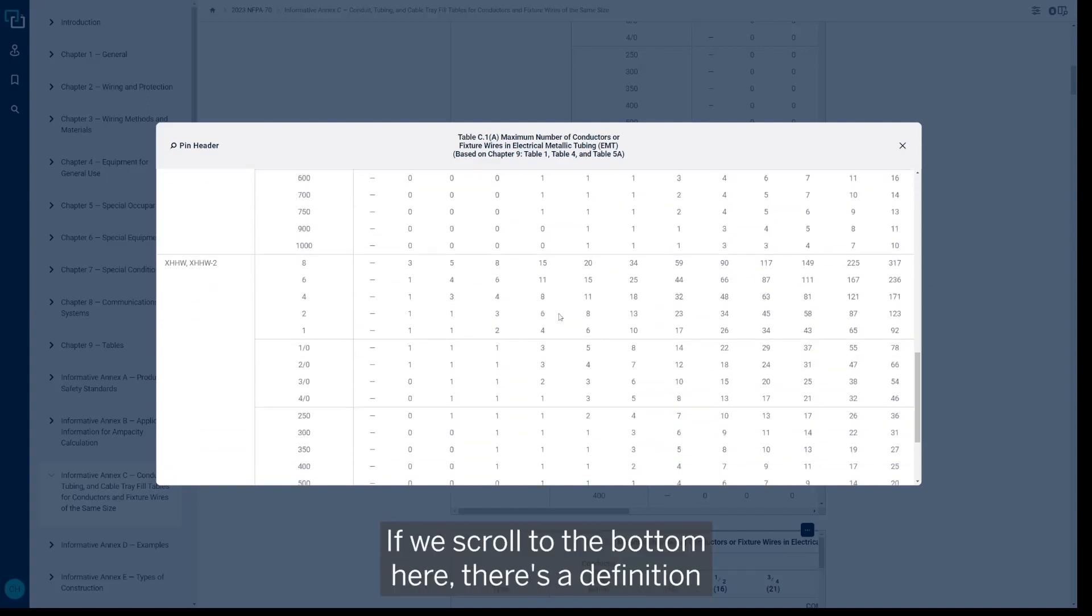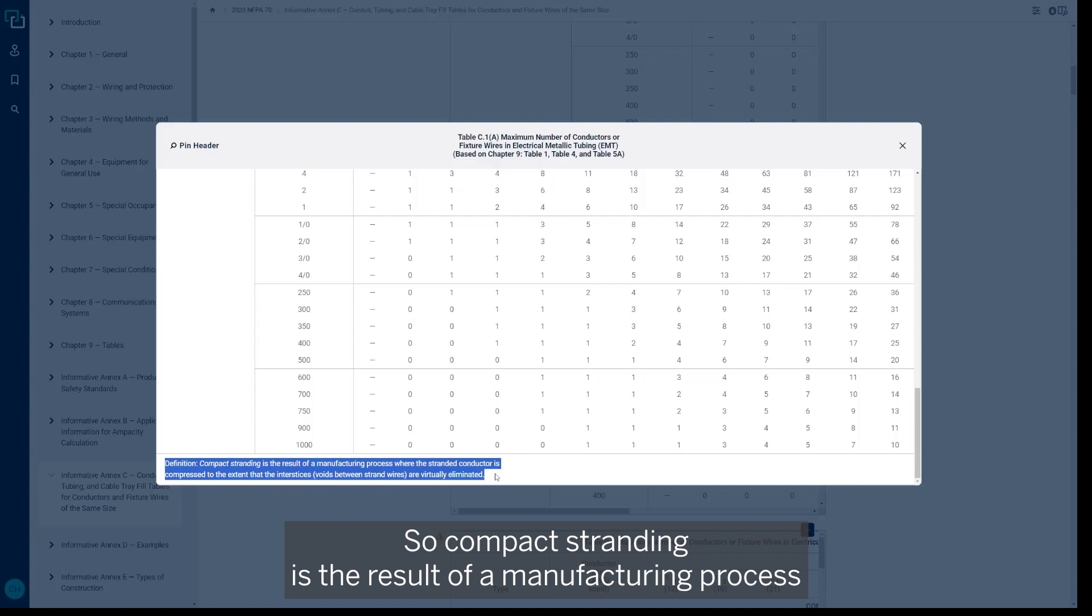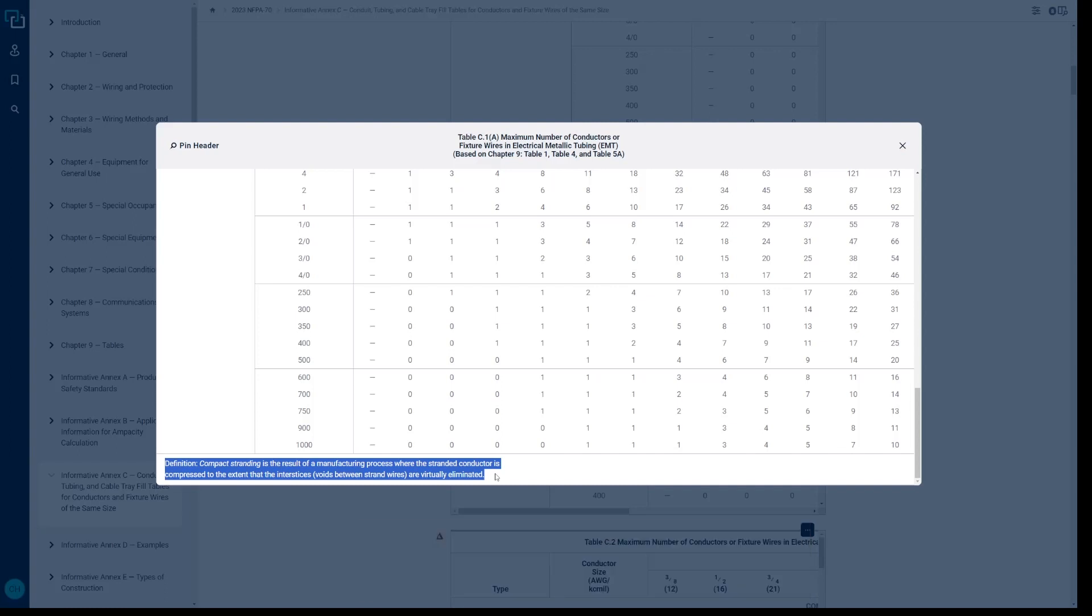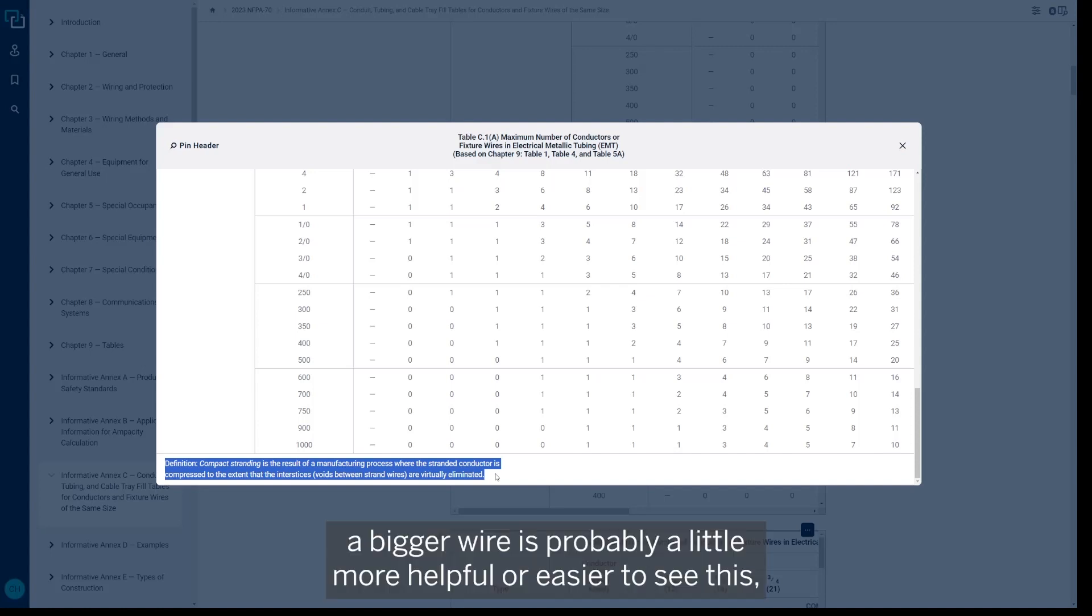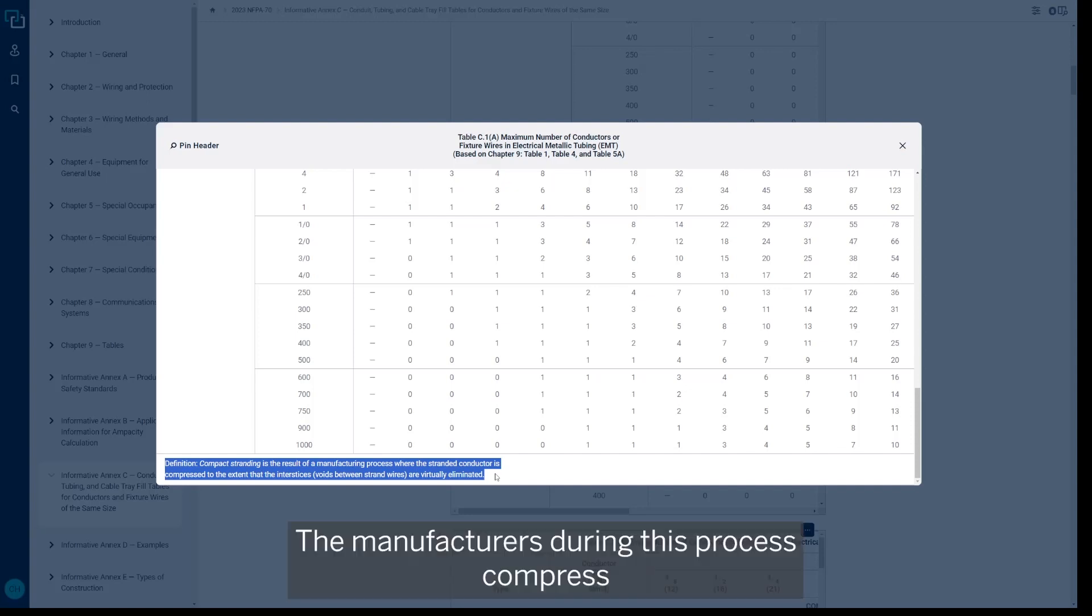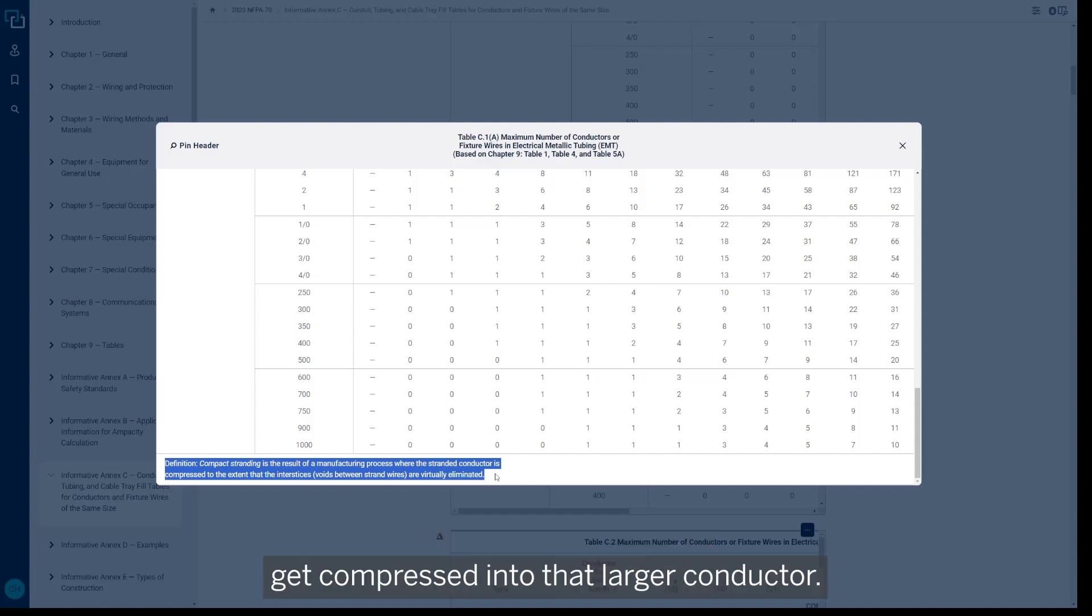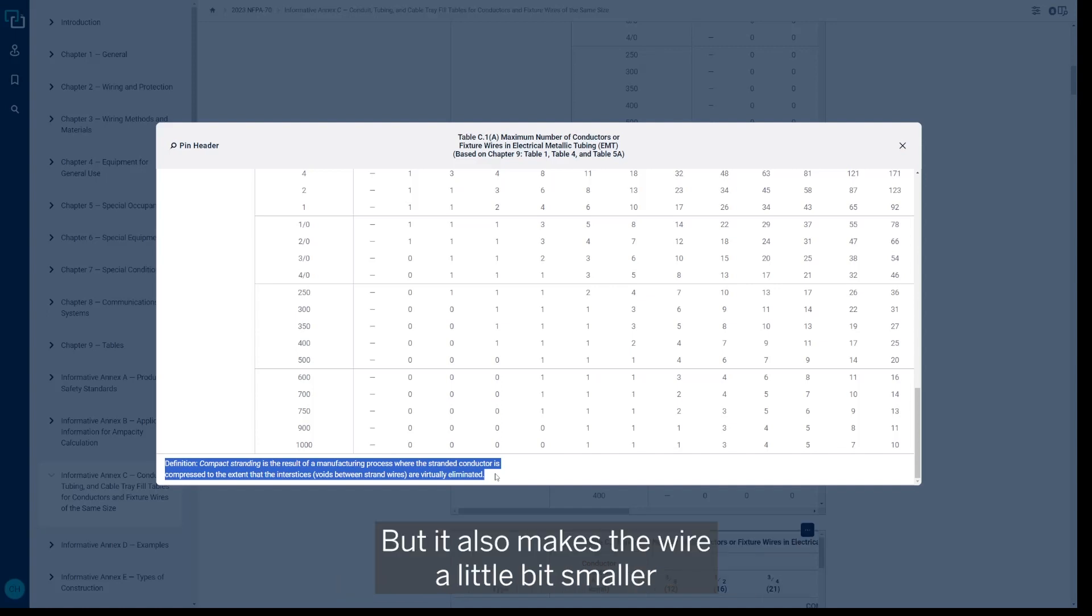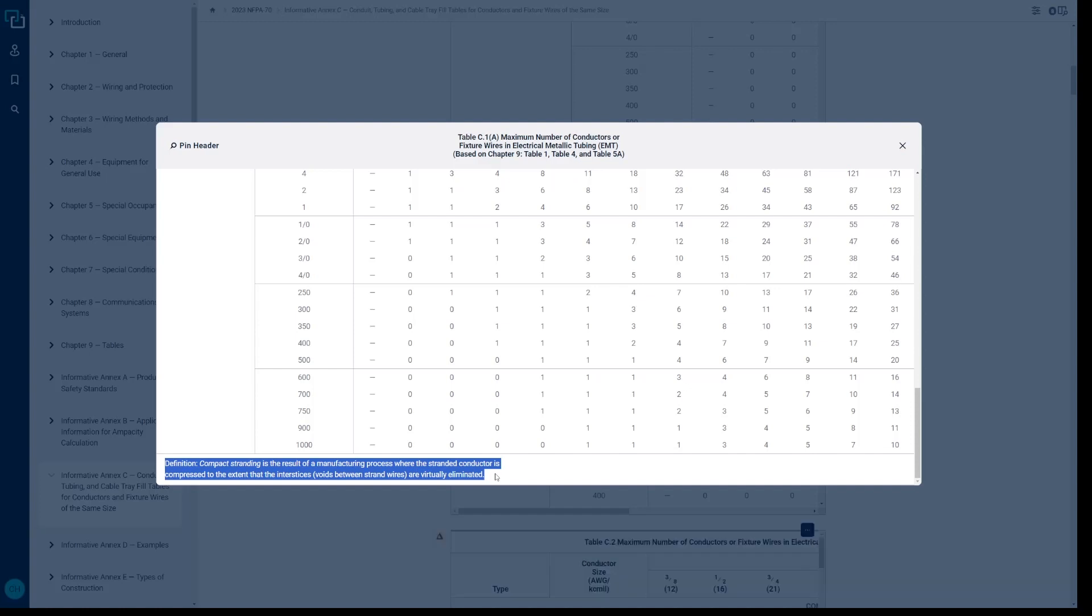If we scroll to the bottom here, there's a definition that we can look at. So compact stranding is the result of a manufacturing process where the stranded conductor is compressed to the extent that the interstices or voids between the strand wires are virtually eliminated. So if you look at the end of a piece of wire—a bigger wire is probably a little more helpful or easier to see this—you can see that there's multiple wires within it that make up that larger overall wire. The manufacturers during this process compress that down, and the airspace that's within those individual wires gets compressed into that larger conductor. So essentially there's less space there within those wires to dissipate that heat because it's being compressed. But it also makes the wire a little bit smaller, in turn making it a compact conductor and usable within this table C1A.